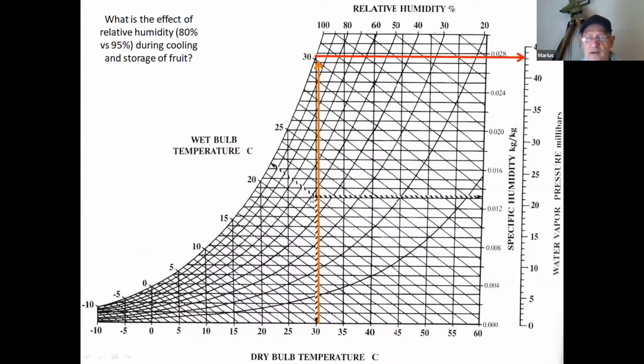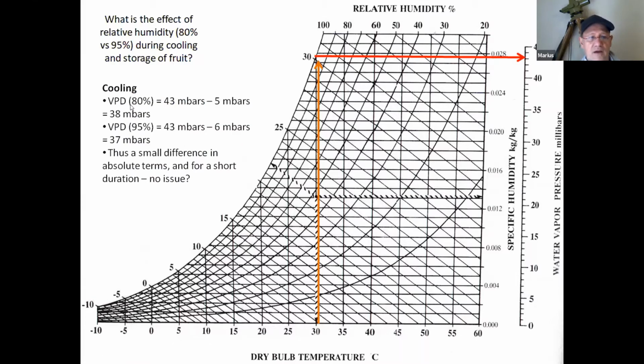There's my fruit at 30 degrees Celsius. We know that the vapor pressure is 43. If I cool that fruit in a cold room with an 80% relative humidity running at 0 Celsius, that's this scenario with the red line at 80% humidity, the third line from the top. So you've got to go down there, run it across. We see that the vapor pressure in the cold room is 5 millibars. So the fruit goes in during cooling, and it's a massive difference, 38 millibar pressure deficit that's driving moisture loss.